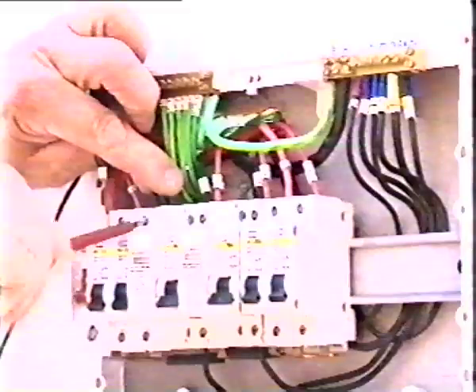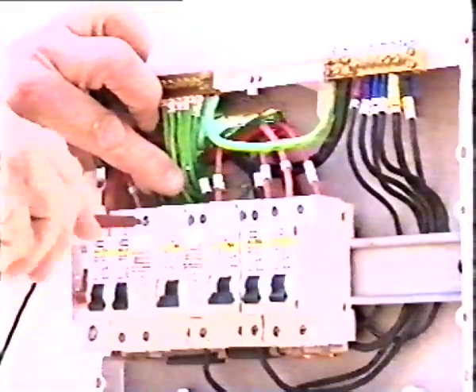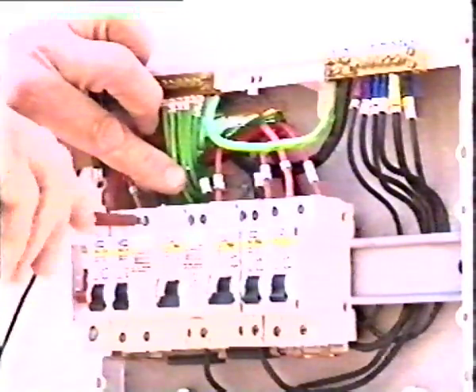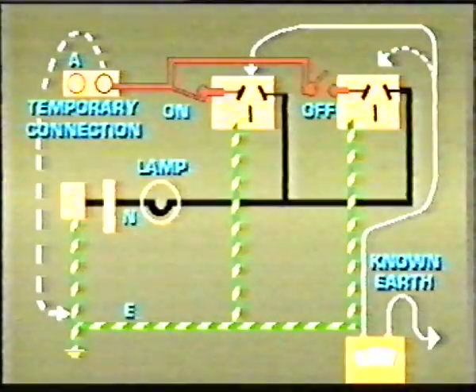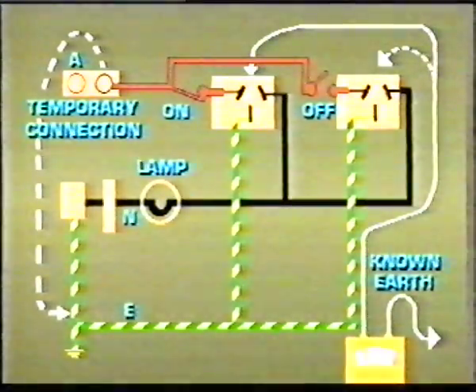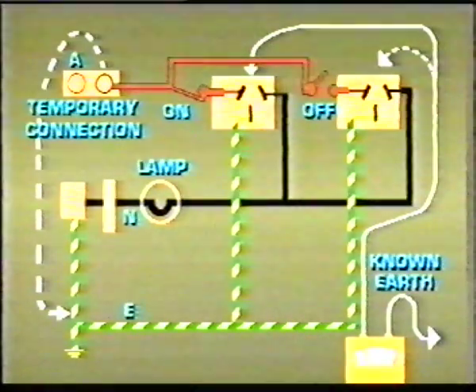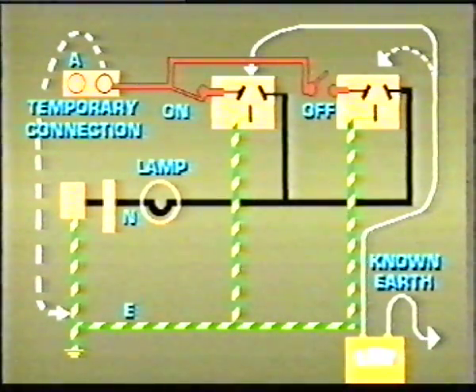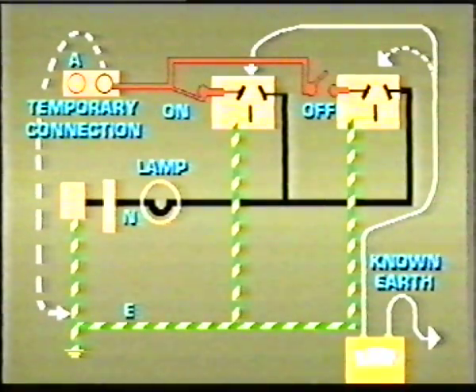Then, a temporary connection is made between earth and the load side of the final sub-circuit's open fuse or circuit breaker. With one lead of the ohm meter connected to earth, the other lead is connected in turn to the active and neutral contacts of the outlet, first with the switch on and then with the switch off.